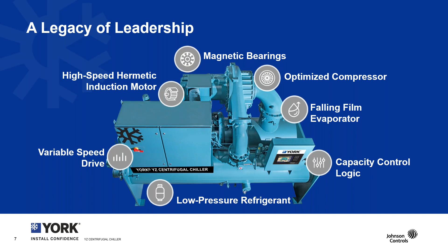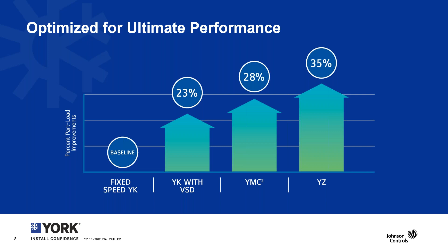As Laura mentioned, our innovations in chillers are focused on moving forward the efficiency frontier, always getting better and delivering part load efficiency, which represents the real world conditions that your chillers operate in your buildings. Our YK, which has been a flagship product for more than 25 years, is an incredible offering, but we've started by adding variable speed drive to that and increasing the part load efficiency 23%. The YMC squared added the benefit of magnetic bearings and reduced friction and increased that to 28% improvement. And now with the YZ, we're pushing forward that frontier again to an unprecedented level of 35% improvement over a fixed speed centrifugal.